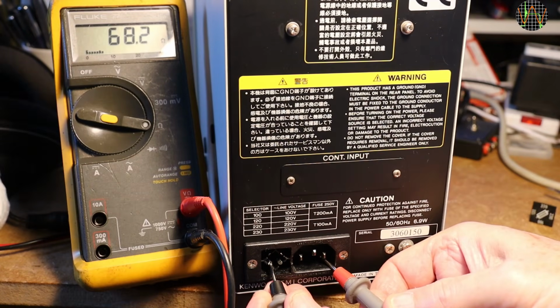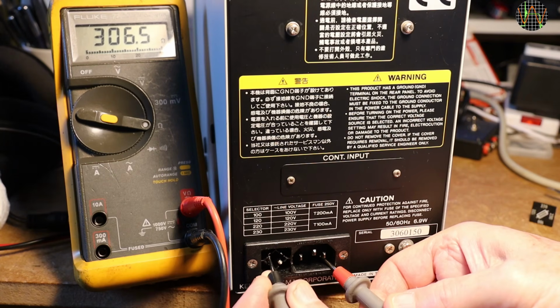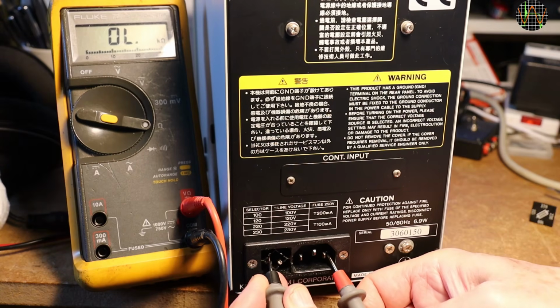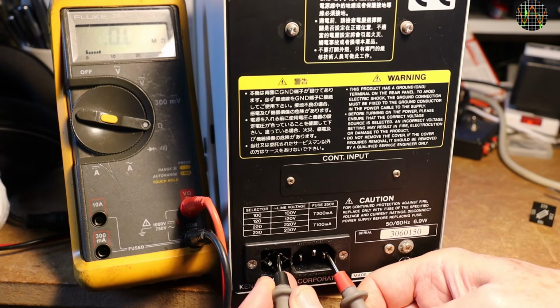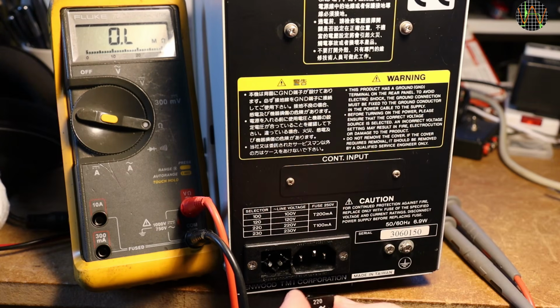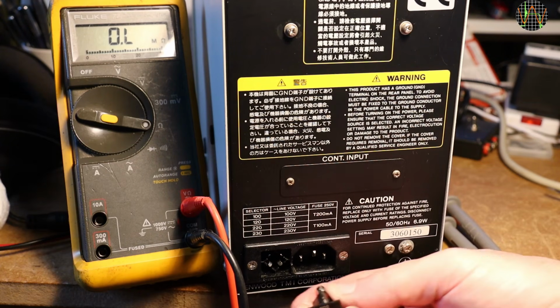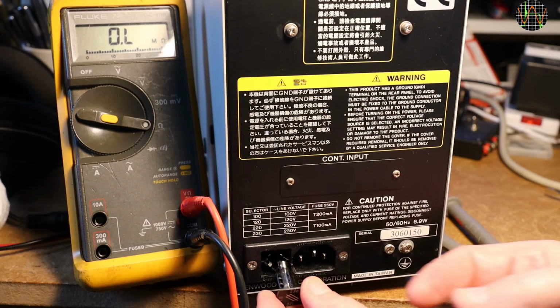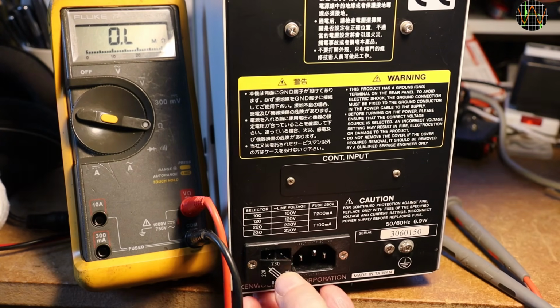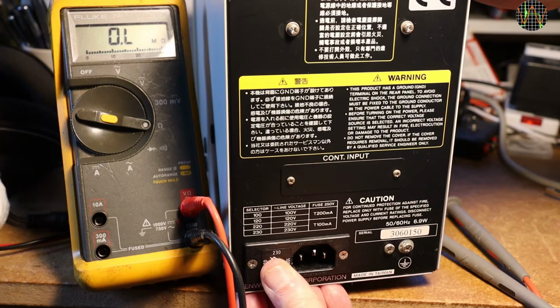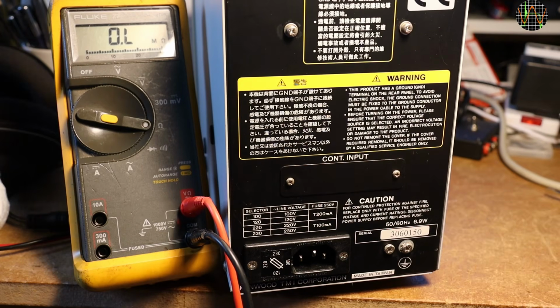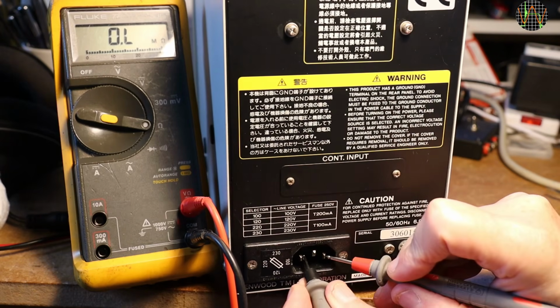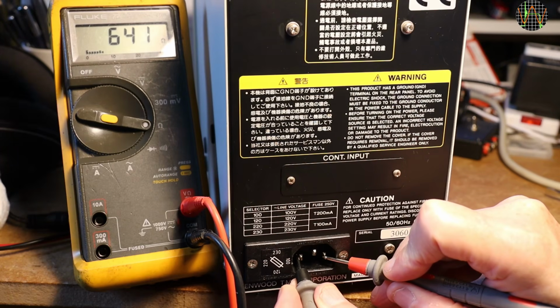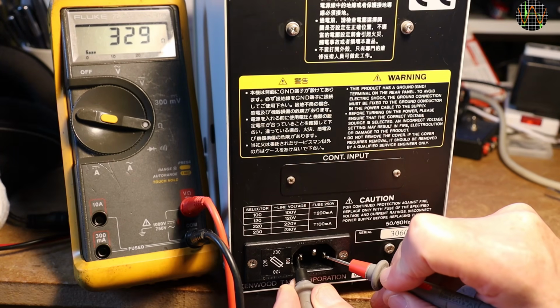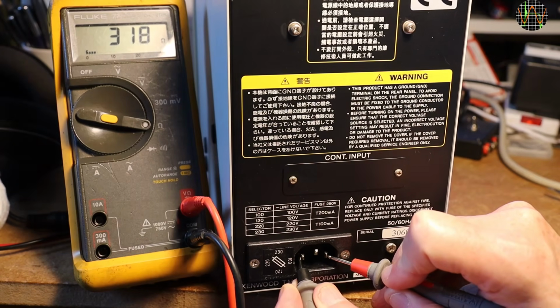Probing the different tabs inside the fuse holder, I'm trying to find the one with the highest resistance, because that will be the 230 volt transformer winding. Interestingly, in this unit this works without turning the power switch on, because the power switch is actually on the secondary side. Anyway, the highest value I saw was over 300 ohm or so. Inserting the fuse holder with a 230 volts oriented correctly should select it. And measuring across the mains connector confirms that the primary for the largest voltage is now selected.